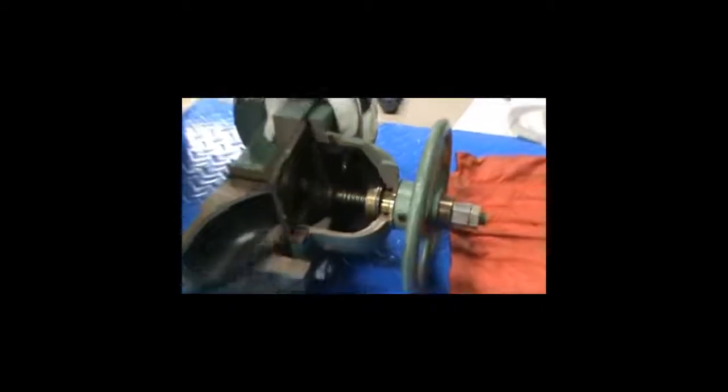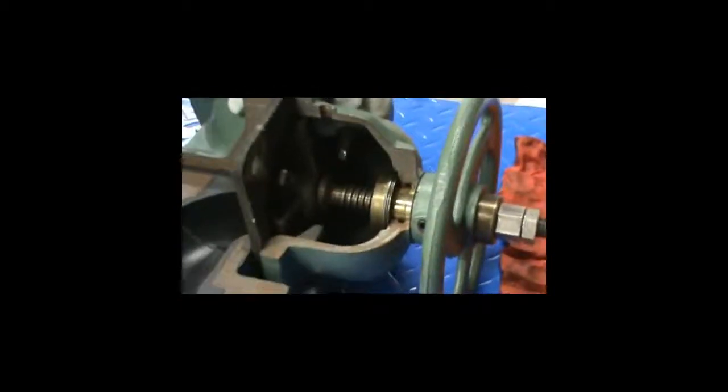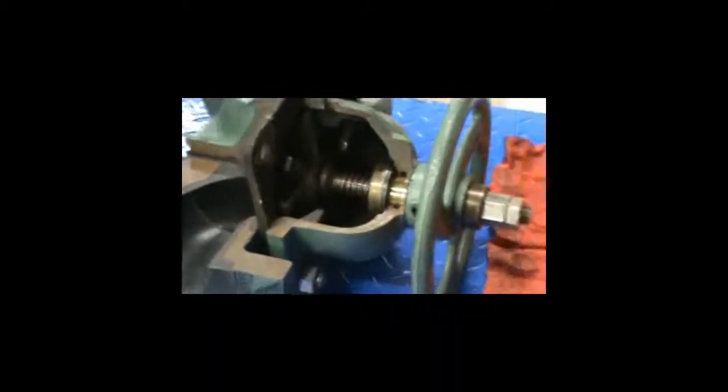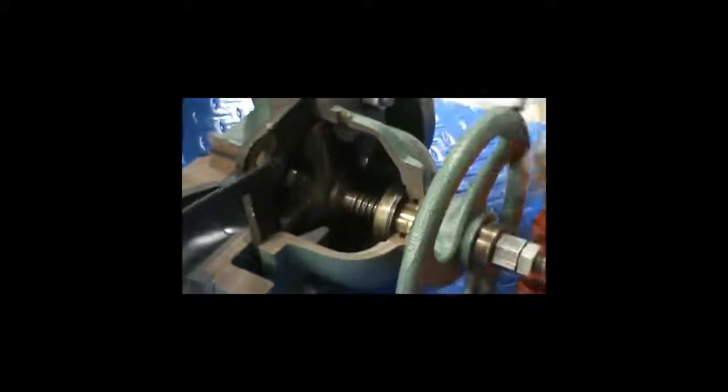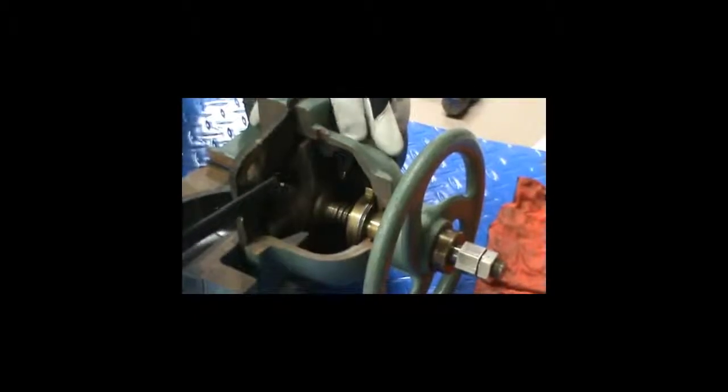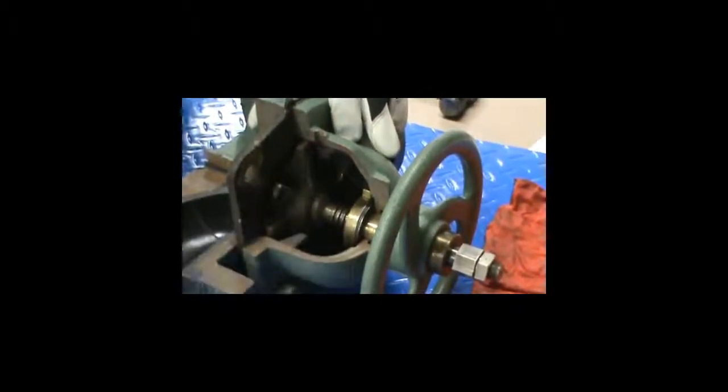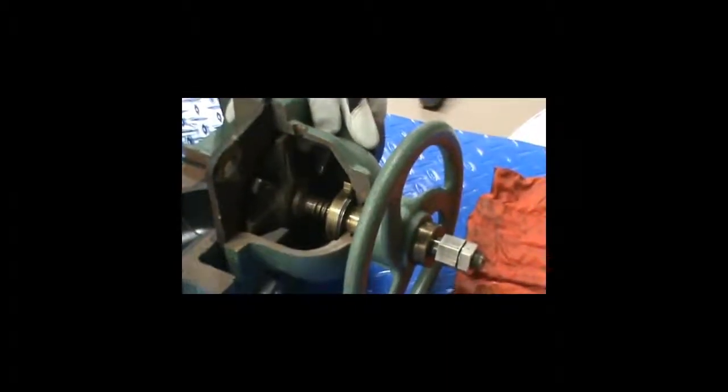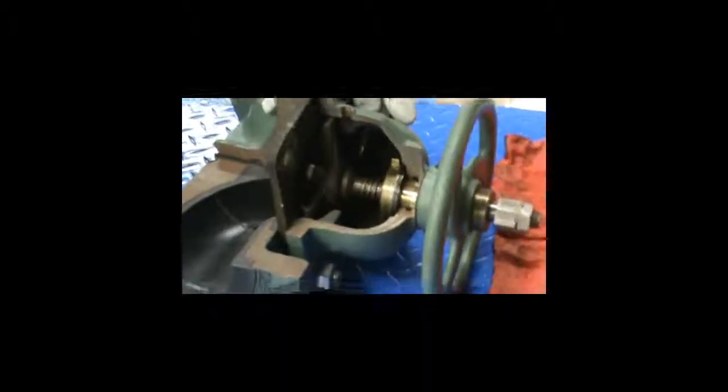Other than that the major components are the body which is right here and the bonnet. This finger, this piece that looks like a bunch of fingers, this is called the compressor. That is attached to the stem which is actually what presses the diaphragm into the weir.